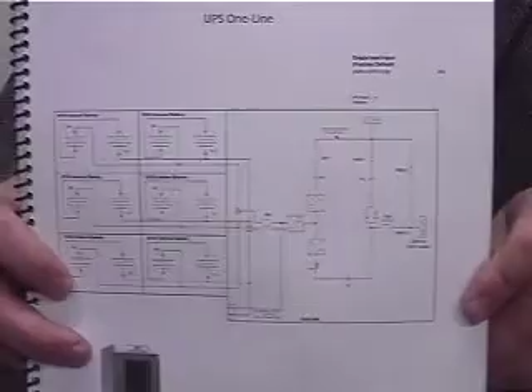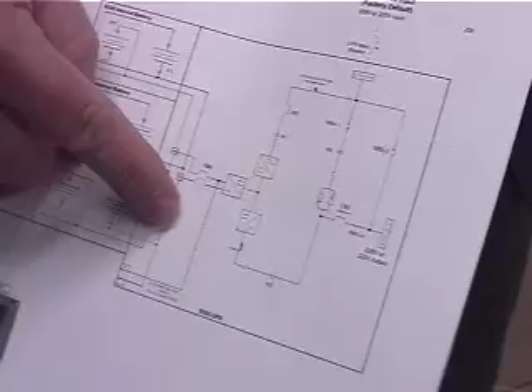If you guys are not familiar with how the one-line is laid out on this unit, there's a bypass switch right down here, which you'll see in this one-line drawing as MBS1 and MBS2. What that does is give you the ability to first transfer the UPS to internal bypass, then you can throw this switch, and once you go to the MBS2 position, you've wrapped around the entire UPS section so somebody can do something in it. The alternate to that would be to have a wall-mounted bypass up here and totally isolate you.